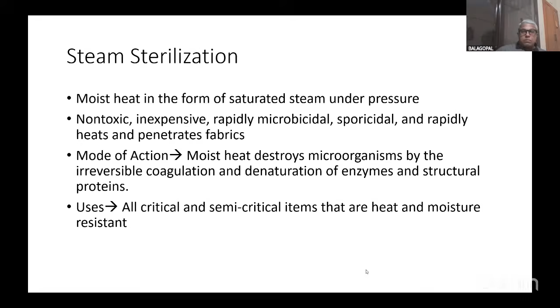The basic principle is to expose each item to direct steam contact at the required temperature and pressure over a specified time. There are 4 important parameters. One is the steam, which involves dry saturated steam at a dryness fraction of 97%, with a high pressure, which is required to obtain high temperature for quickly killing the organisms. The temperatures range from 121 to 132 degrees centigrade.